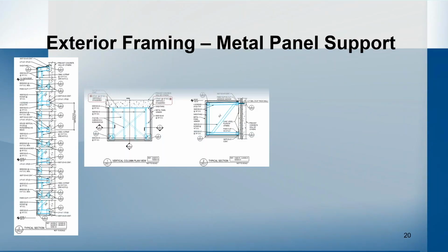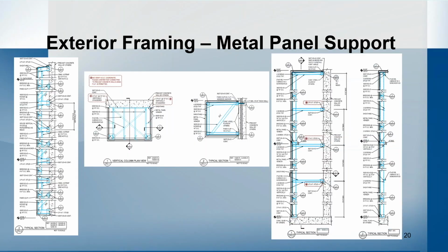And these are some of those typical details that we're seeing with the metal panel connections going to precast or to the tilt panel. In the middle there, that's where I was talking about the thinner outer concrete layer and then the insulation. We had a canopy that we couldn't feasibly make the connection work with a shallow type anchor due to limitations of the concrete. So we had to use a deeper anchor with an adhesive that went all the way through to the thicker portion of the concrete. But these are common type details that we're using on a number of data centers here in the Mid-Atlantic market.